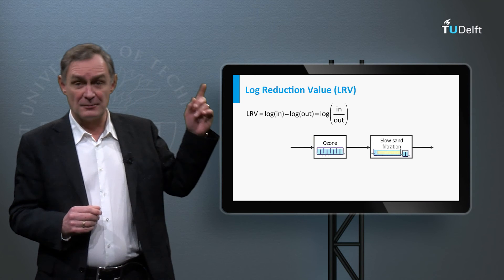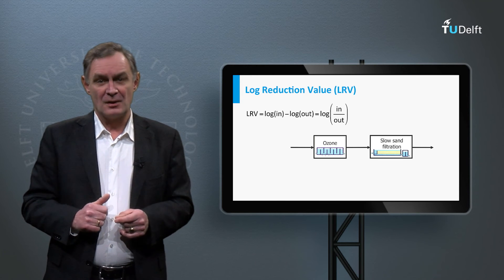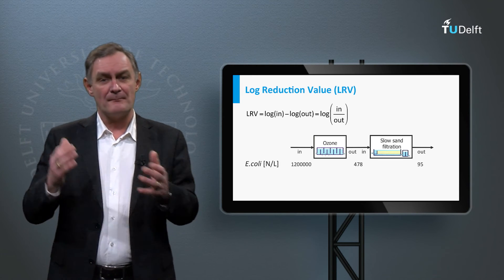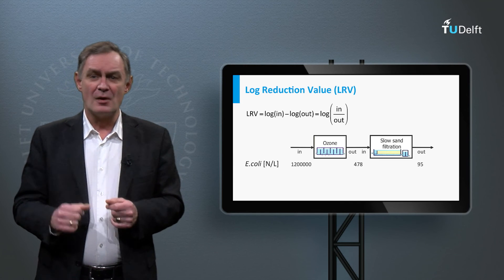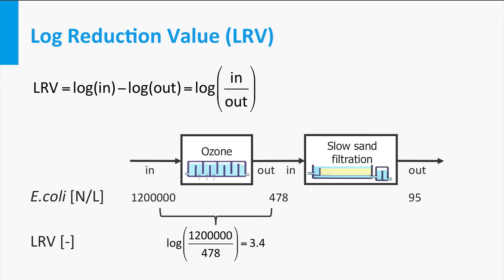2 log removal is equivalent to 99% removal and 4 log removal is 99.99% removal. As an example, a multi-barrier system is shown: first ozonation and then slow sand filtration. The incoming number of E. coli per liter is 1.2 million and the outgoing concentration after the ozone treatment step is 478 per liter. The log reduction value is then 3.4. Adding the log reduction value for the slow sand filtration gives a total log reduction value of 4.1.